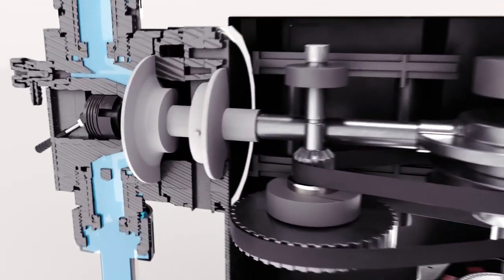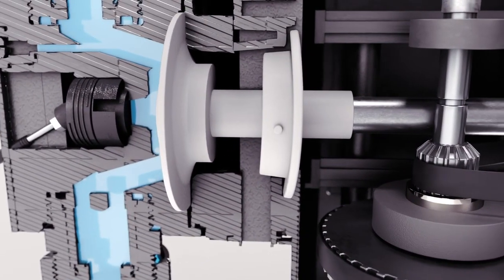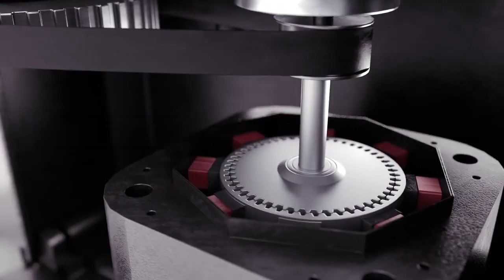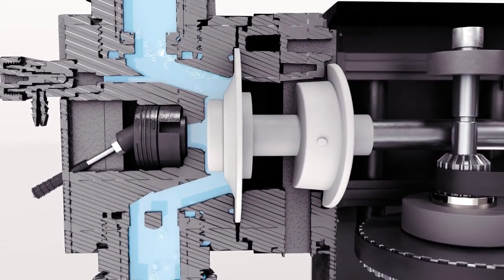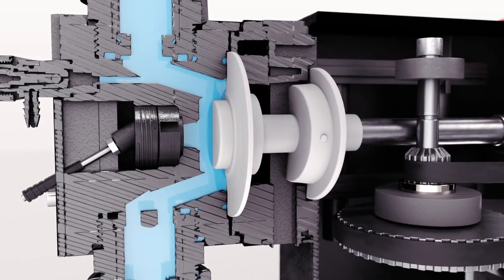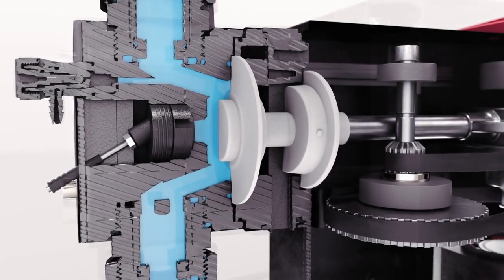An integrated pressure sensor in the dosing pump detects gas bubbles and sends a signal to the stepper motor to adjust speed. The air is then purged out of the dosing head, preventing vapor lock and loss of prime that can lead to downtime and improper treatment.